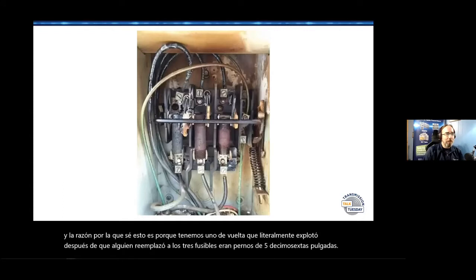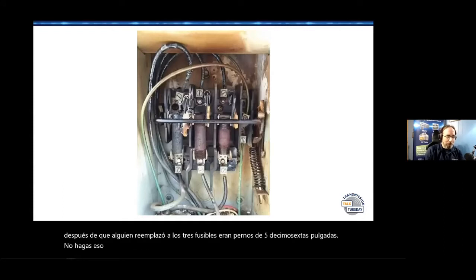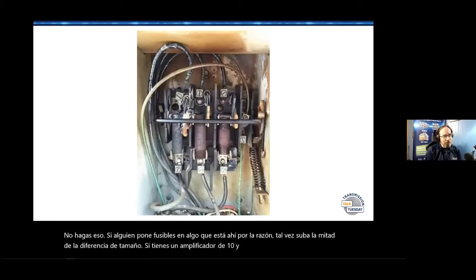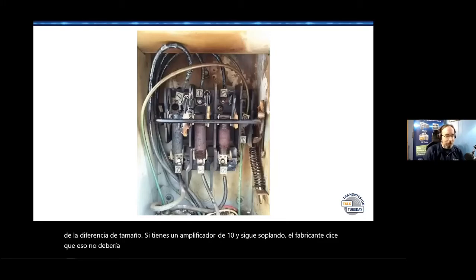Don't do that. If somebody puts fuses in something that's there for a reason, maybe go up half a size. If you've got a 10 amp that keeps blowing and the manufacturer says it shouldn't do that, try a 15. But not bolts. Just don't.